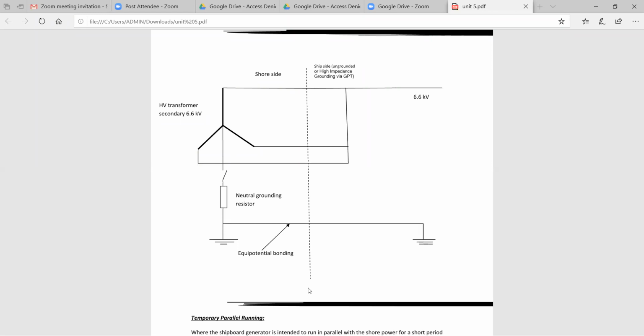If we have a star connected system and the neutral line is disconnected, the voltages VRN, VYN and VBN are not equal. That means unbalanced voltage acts between VRN, VYN as well as VBN. So the neutral is properly connected with the resistor, and you have one switch. When the switch is closed, the neutral line along with the resistor is connected to the ground system. So whenever you need grounding or equipotential bonding operation, you can close the switch. Automatically the closing operation has to be performed in this network.